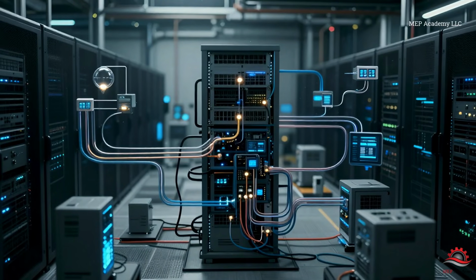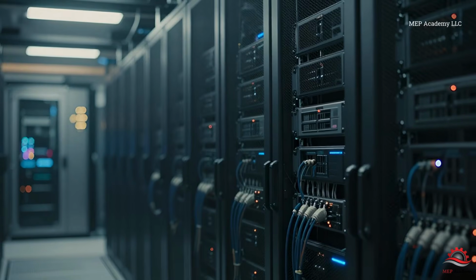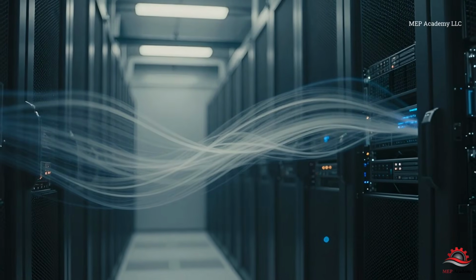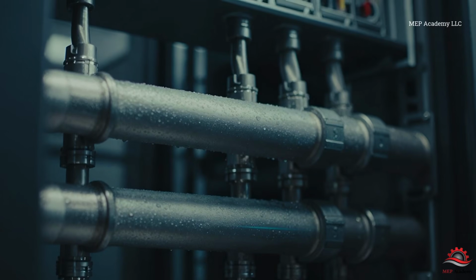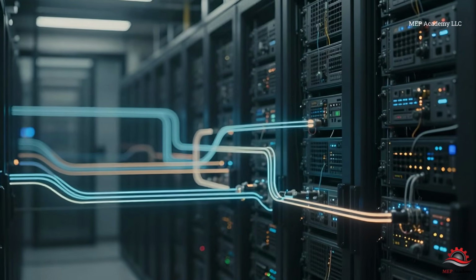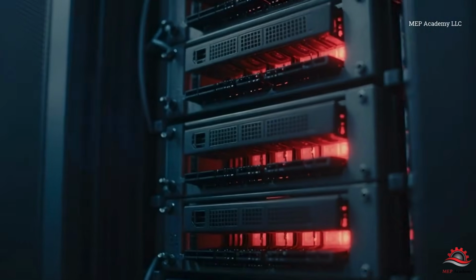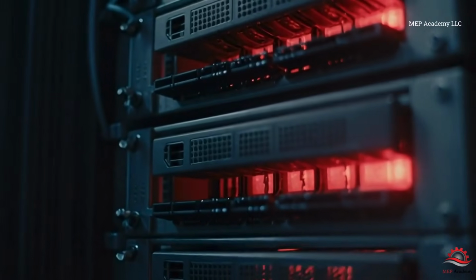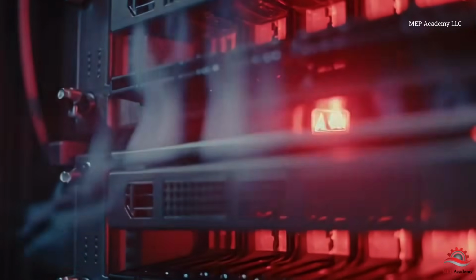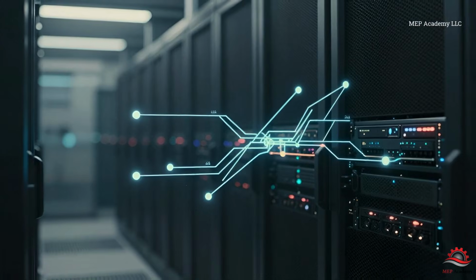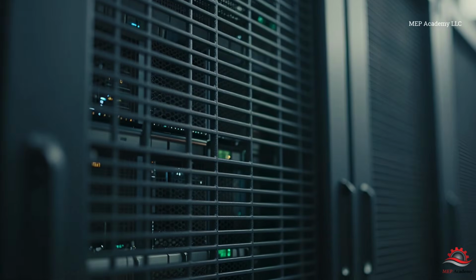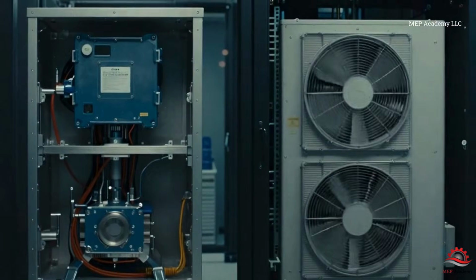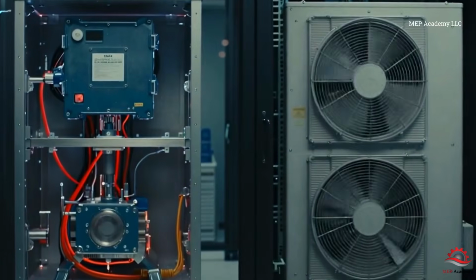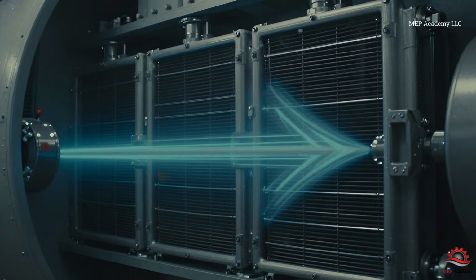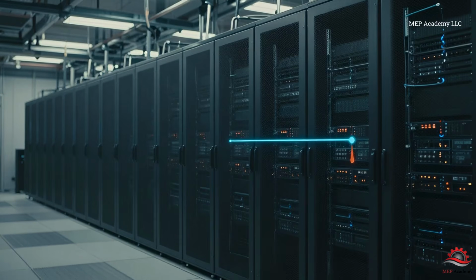Let's zoom out and connect everything we've covered so far in this series. Power systems keep the servers running. Airflow systems manage how air moves through the racks. And chilled water systems remove the heat from that air. All three systems must work together perfectly. If power fails, the servers shut down. If airflow is poorly designed, cooling becomes ineffective, and if chilled water fails, the entire system overheats. This is what makes data centers so unique. Every system is interdependent. In the next video, we're going to zoom in even further and break down the difference between CRAC units and CRAH units. Because understanding how those units actually deliver cooling is critical to understanding the full system.